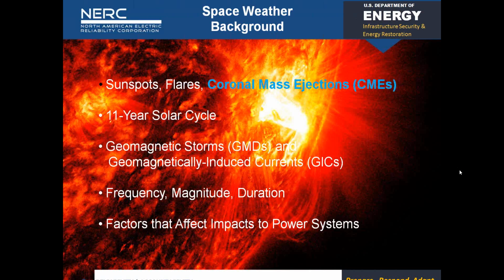Characteristics of the geomagnetic disturbance also matter, not just the size of it, but the orientation of your system to the pulse and how long it actually lasts. Other factors that come into play are the latitude you're at - more northerly means more susceptibility - soil conductivity, which USGS looks at, and whether you're close to large bodies of water. Having a lot of reactive power reserves can help if you have a large one, and Mark may get into that a little bit.